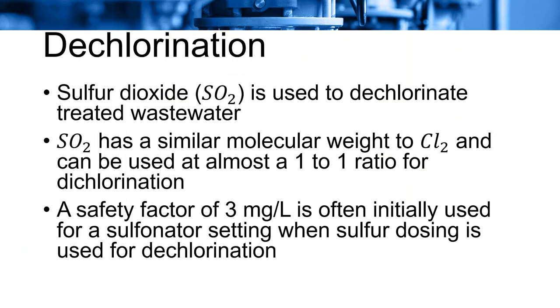All right. So, we're going to move on from breakpoint chlorination, and we're going to talk about dechlorination. Just real quick, dechlorination can be accomplished by a variety of things: time, light, oxygen. But a common usage is sulfur dioxide to dechlorinate treated wastewater. The reason is that sulfur dioxide has a similar molecular weight to chlorine and can be used at almost a one-to-one ratio for dechlorination.